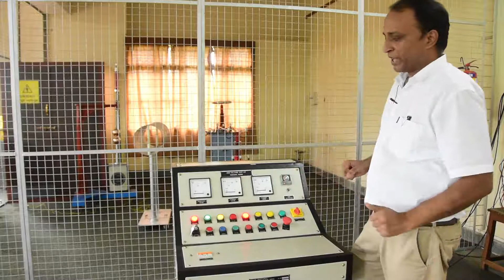At the same time, one very important thing to note is that while working for audible corona, we have to ensure that all the fans in the lab are switched off. Also, if there is a large group of students present here, then silence must be maintained in order to have clarity and the correct reading for observing the audible corona. Because if there is noise present, then the audible corona inception voltage will not be known. We want to check where the audible corona starts. Once it has reached and gone above that level, it will keep on making a noise. So we want to find out at what voltage the audible corona just begins.